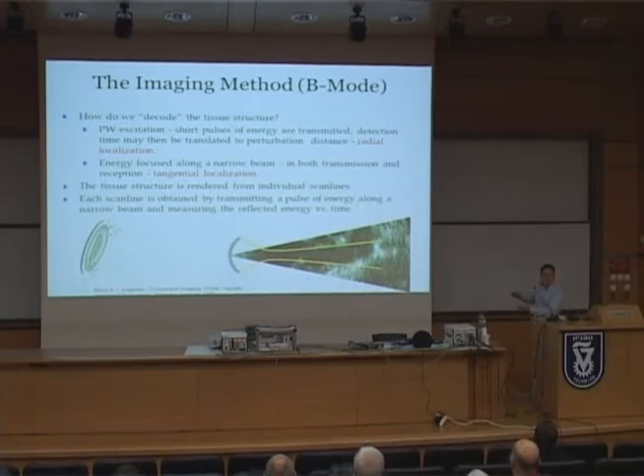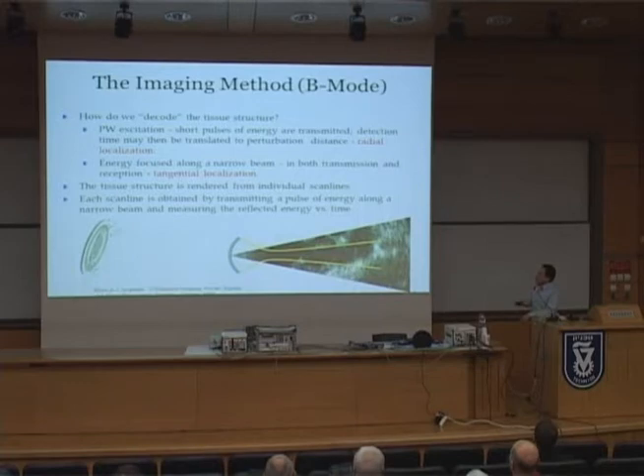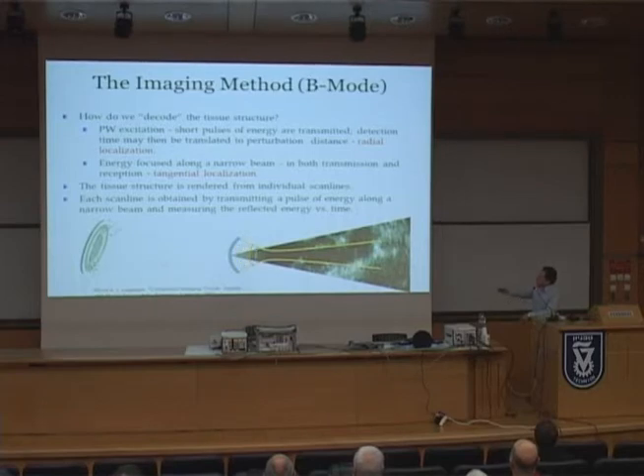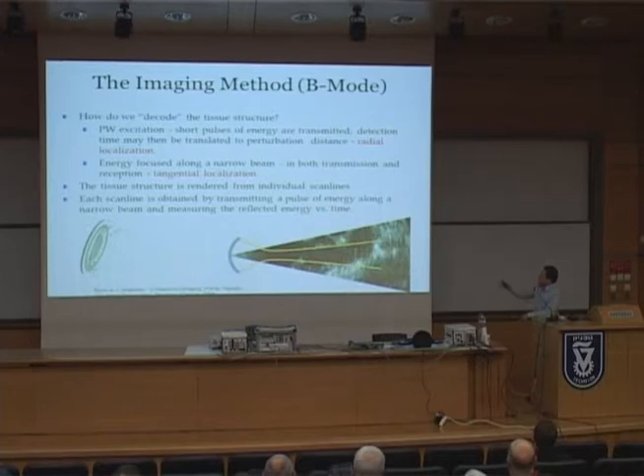We additionally need to obtain tangential or angular localization, and this is done by focusing the energy along a narrow beam both in transmission and in reception. Basically, the tissue structure is rendered from individual scanlines where each time we transmit a single pulse of energy, we detect the reflected energy and map it versus time, and then this beam is steered in the plane or in the volume.